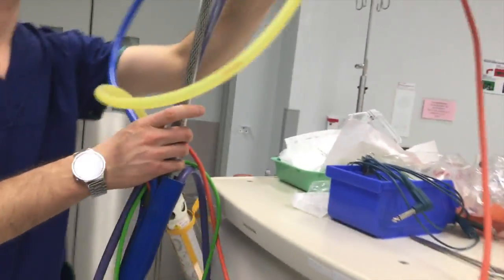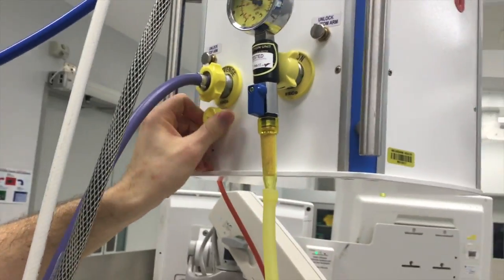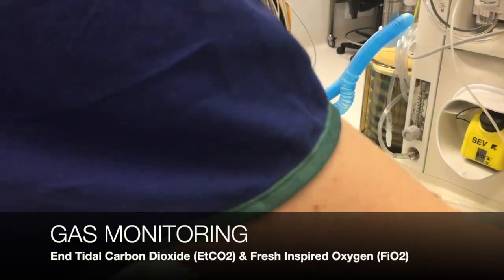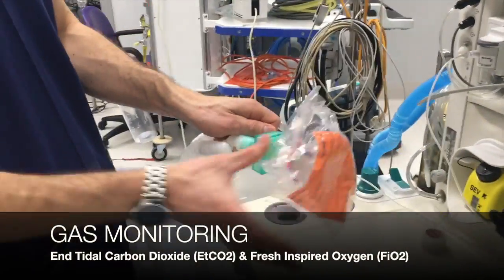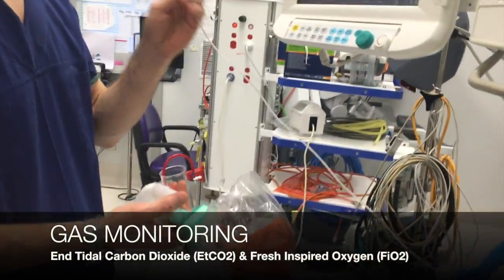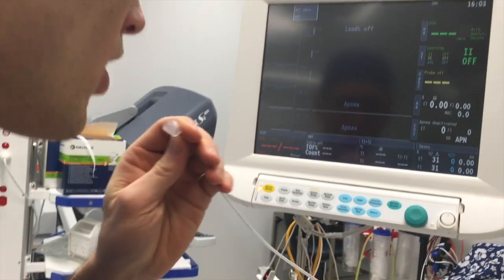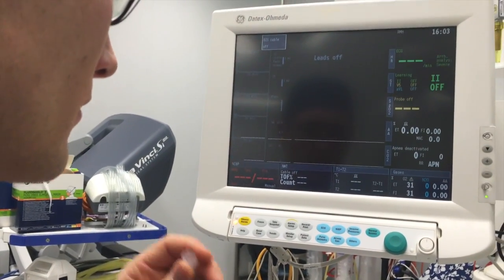One of the final checks is to ensure that scavenging is connected and turned on. This is a continual amount of suction that takes away any waste gases from the anaesthetic machine. Now that the machine is ready, check that your gas monitoring is working by blowing on the CO2 sample line and waiting for the capnograph waveform to respond.